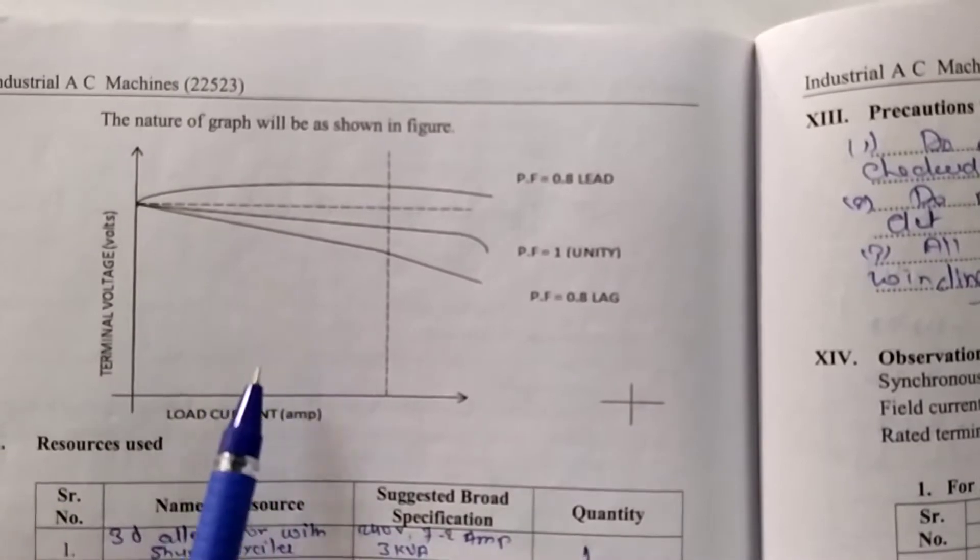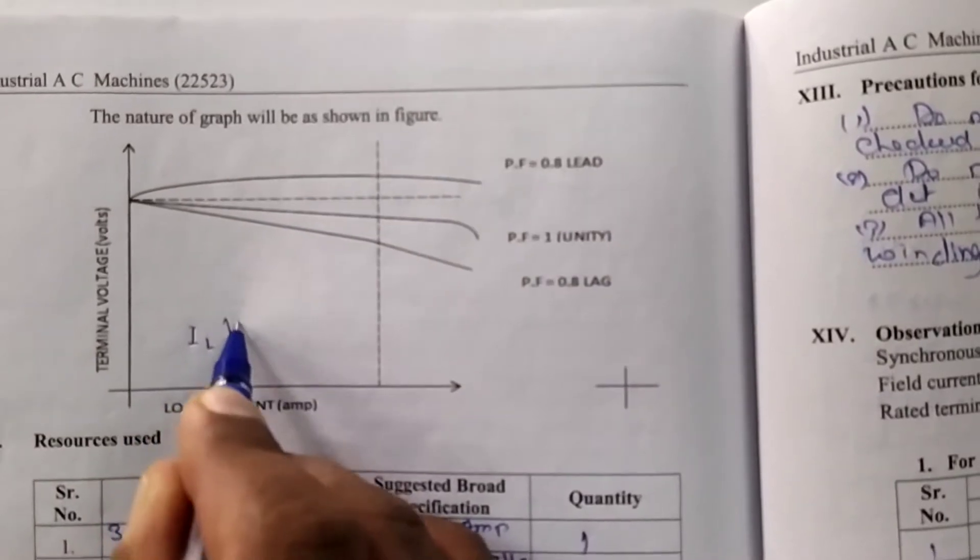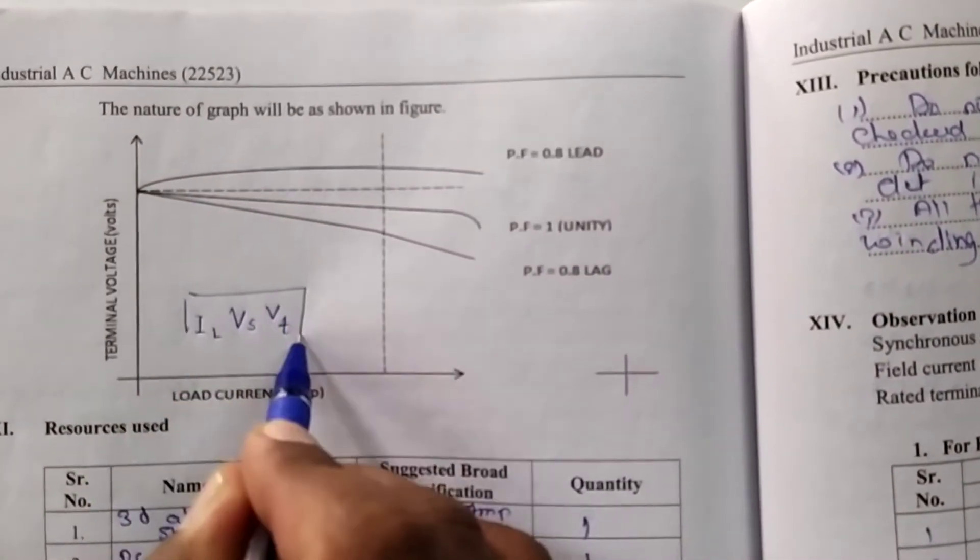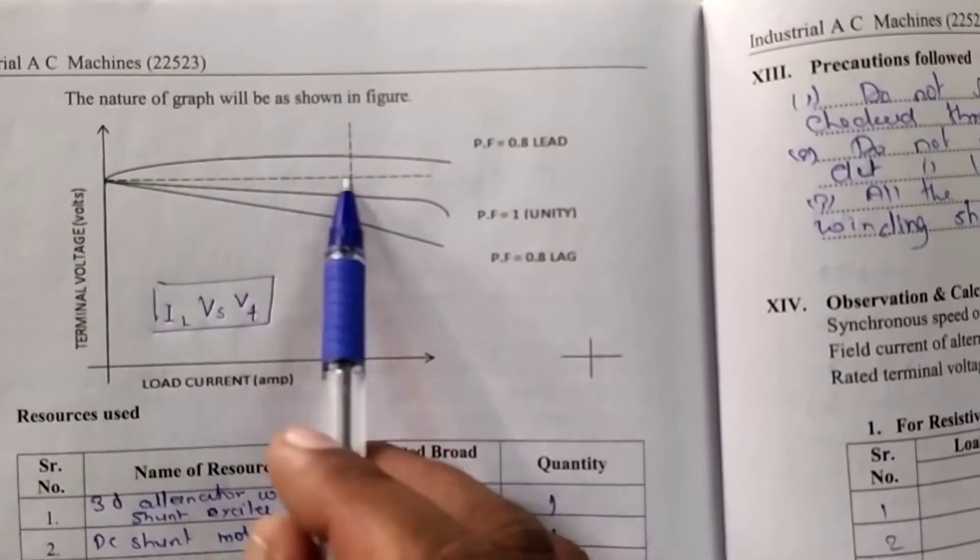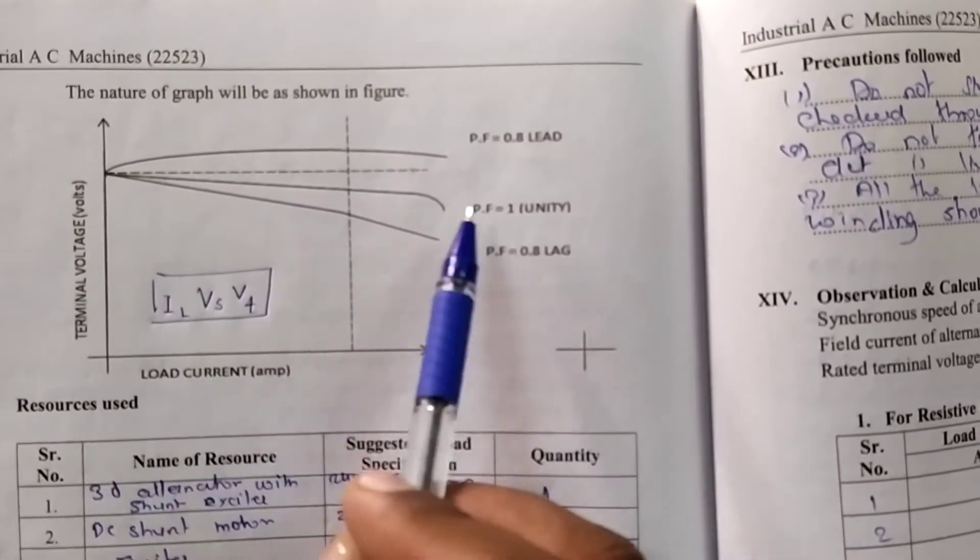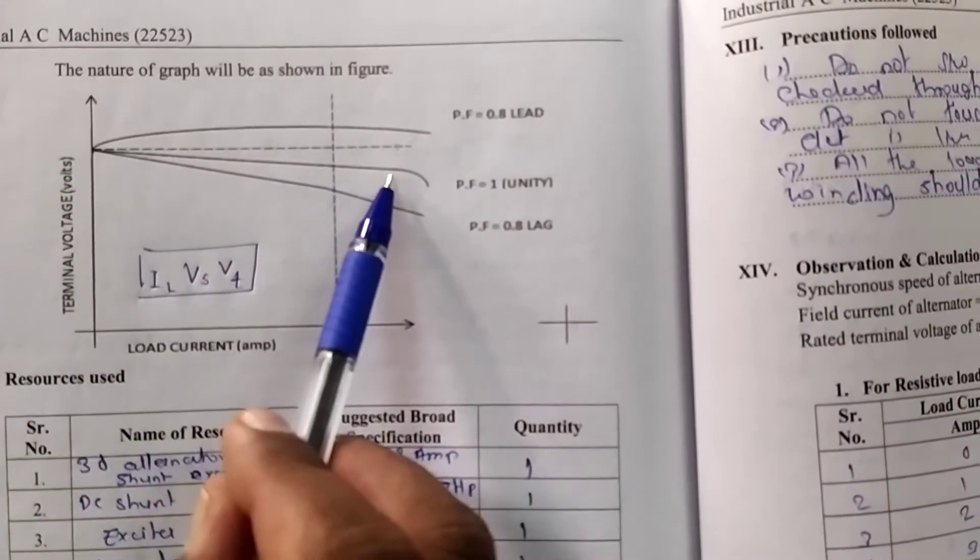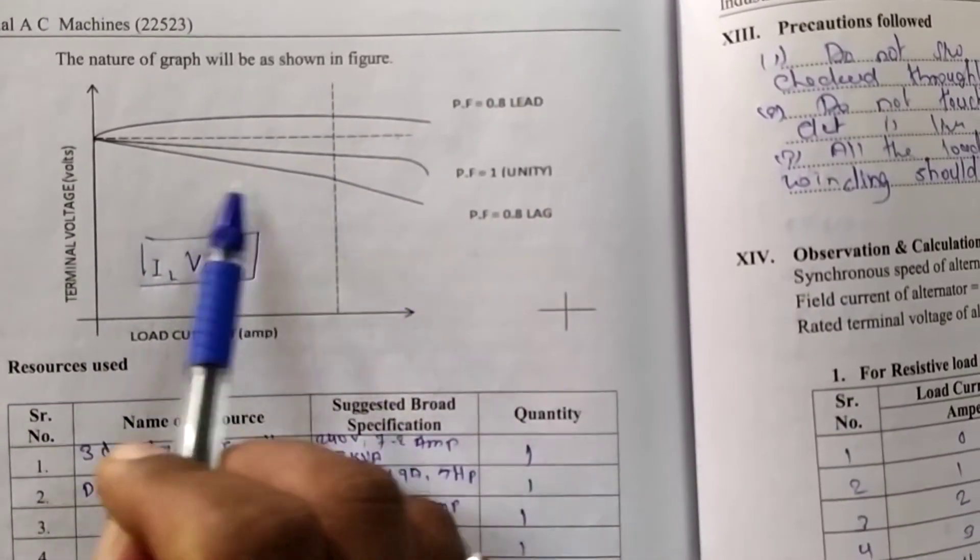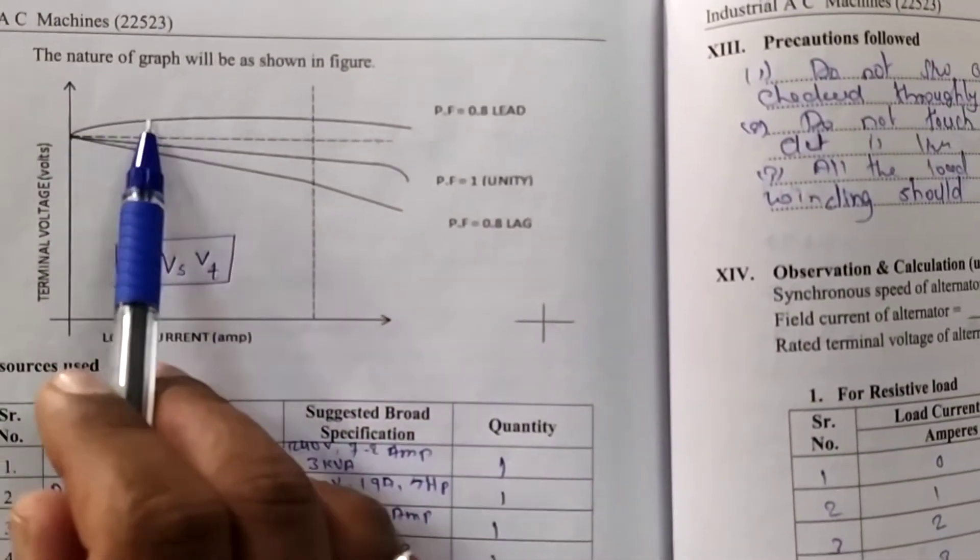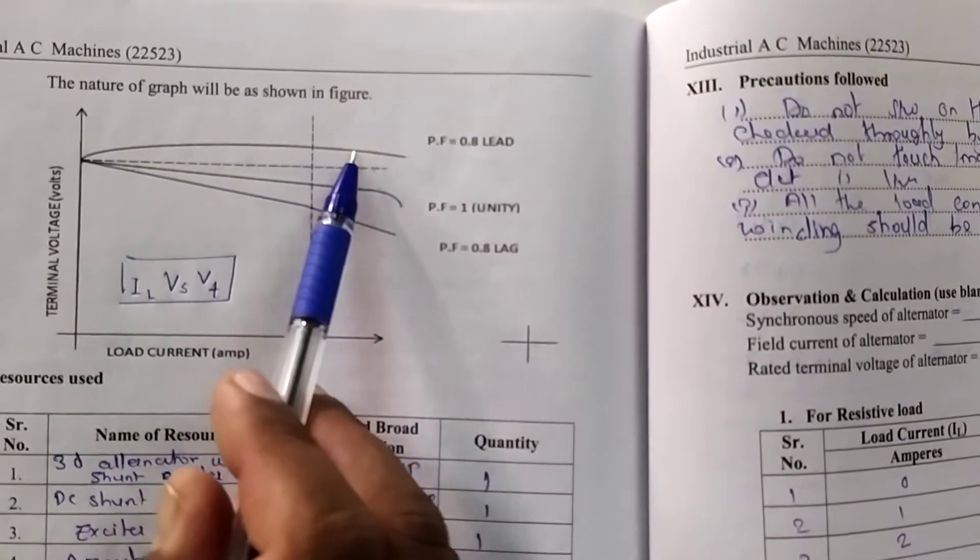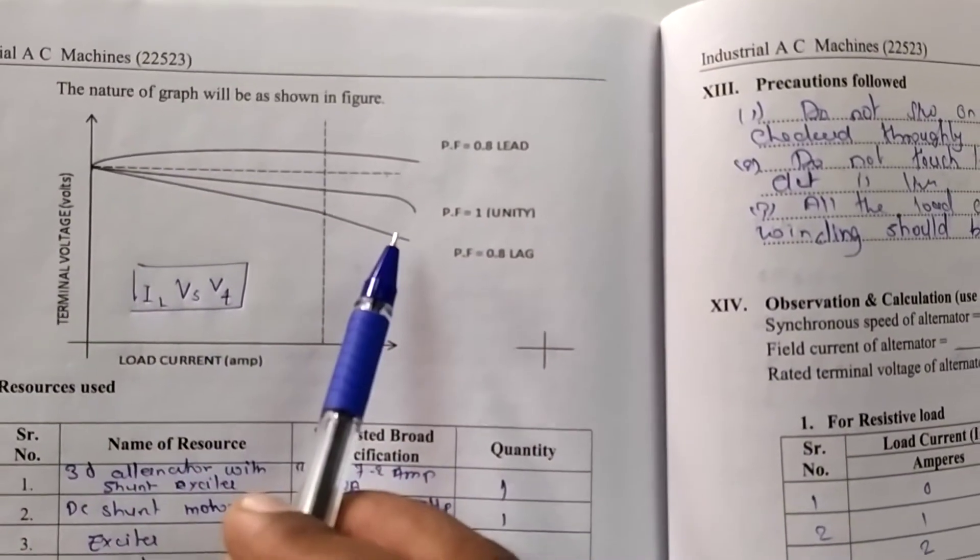Plot the nature of graph means load current versus terminal voltage, IL versus VT graph. From the graph, it is clear that this is the ideal voltage line. And for resistive load means power factor is unity, as the load current increases, the load terminal voltage slightly decreases. For inductive load, the voltage drop ratio is slightly increases. And for capacitive load, the voltage increases from its rated values. Hence power factor is 0.8 leading, unity and lagging.